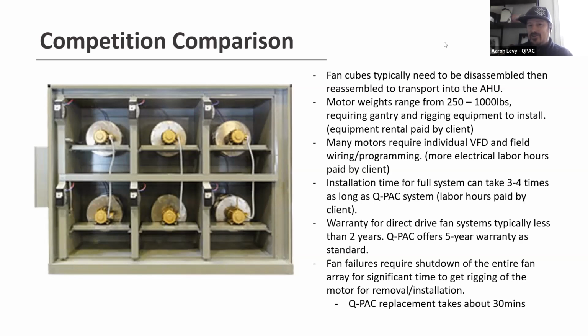It takes a lot longer to install those because you have to sometimes disassemble those cubes to get them into the space, then reassemble them later, versus just being able to carry everything into an airspace, putting it all together in one big motion, and being done in a day. There's no programming that needs to be done. We've taken that all into account on our side. Therefore, it cuts down on a lot of your electrician's labor hours, as well as programming. Labor time is the biggest savings that you can get for getting jobs done. Normally, the demolition of the old unit takes longer than it does to install our system.